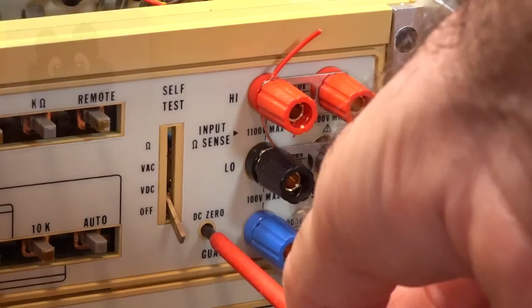Sheesh, something is off. I can't zero out the DC ranges. The front panel has a little trimmer to compensate for tiny offsets, so that should be plus minus 30 counts. But the signal is so much all over the place that I can't tell if it's doing anything at all.